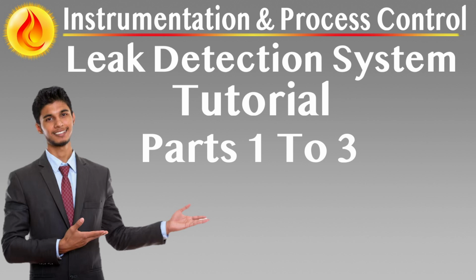Reliability refers to the LDS's ability to accurately distinguish between true leak events and benign operational variations. A reliable system consistently detects real leaks without generating frequent false positives. Reliability is primarily a function of the leak detection software and algorithms, independent of external hardware performance. However, it is highly sensitive to signal quality from instrumentation. Systems that rely on model-based calculations may require frequent recalibration or tuning to maintain reliability, especially in pipelines with changing operating profiles.